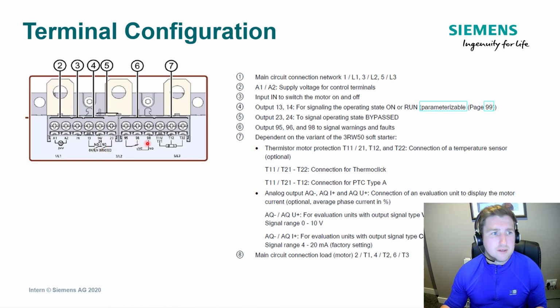Number 95, 96 and 98 are specifically for signaling for faults and warnings. So I mean, it doesn't tell you in great accuracy what those faults and warnings are, but you could link that up to an output, which could be an illuminated push button, which would signal to an engineer that there was a fault or a warning that they might need to look at. T11, 12 and 22, these can either be a thermoclick or a thermistor sensor, or you can even have that as an analog output, so you can monitor the voltage or current through an external device, whether that be a current meter, an amperage meter or a voltmeter.